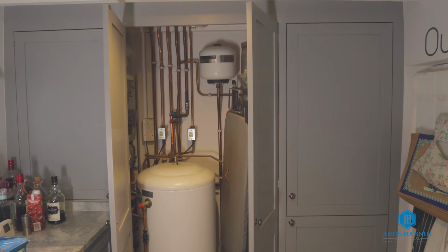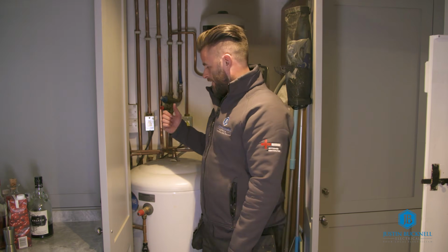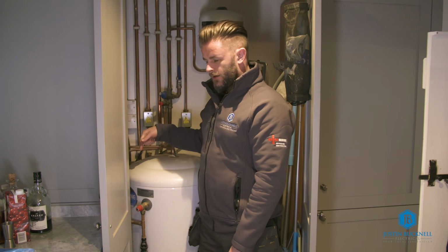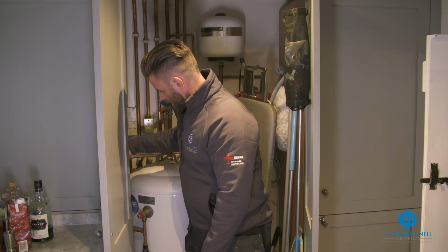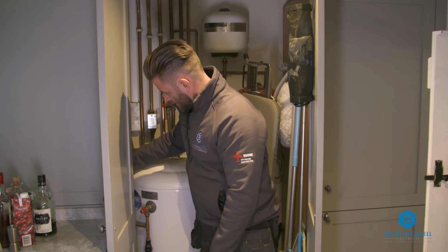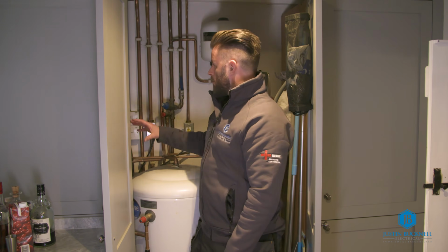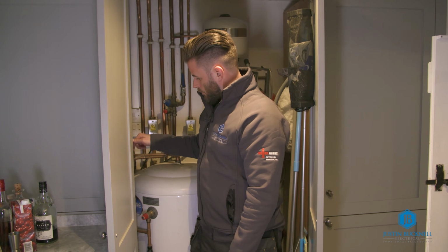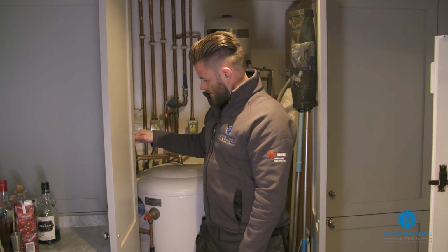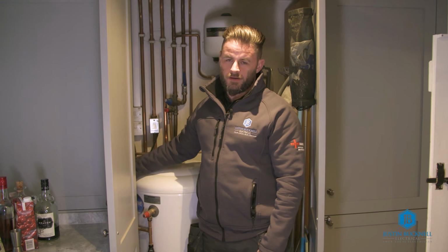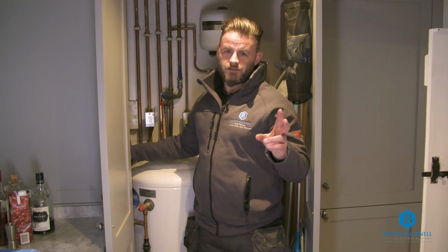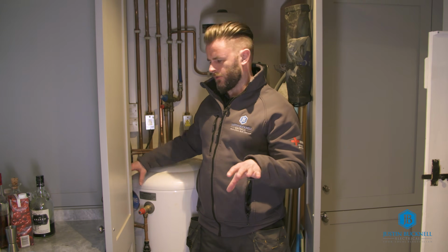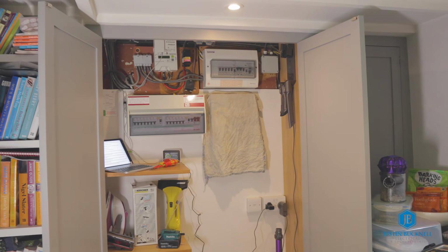Okay. So we've been outside and checked the oil line coming into the property. It comes in low level down here, which is hidden a bit out of sight, so we can't really get the camera in there, but we can see that there is absolutely no bonding cable in this cupboard, and certainly one that doesn't make a connection. There's not one that makes a connection onto the oil supply at all. So we're going to have to do some further checks and investigation to see what's going on there, because we cannot find the bonding for the oil at all.